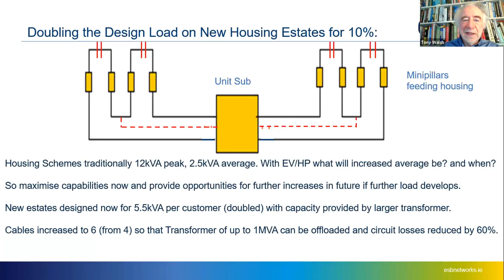So the savings in losses pays for those cables. Similarly, if we ever needed to increase the size of this unit sub from 630 to 1 MVA, we now have 6 cables at 200 kilowatts a cable, so we have more than enough cable capacity to offload the unit sub.